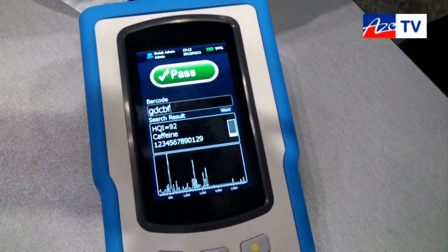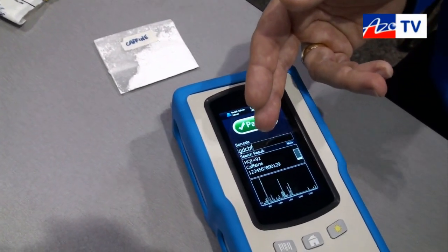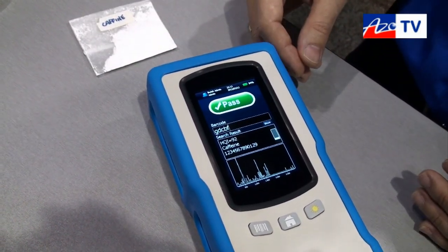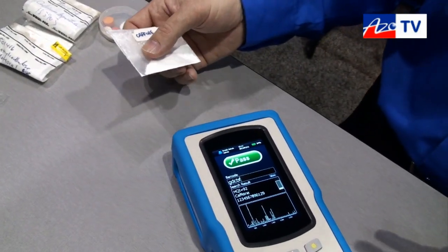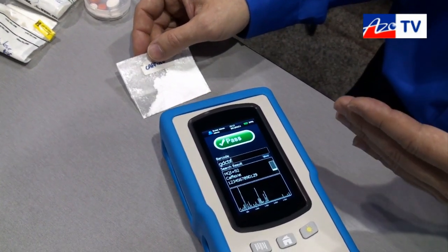Within seconds you have your answer. The product has been identified as caffeine — and that is what it is. You can see the system provides what is called HQI, the Hit Quality Index. It's a score indicating how good a match there is against the reference in the library. In this particular case, because there's a plastic bag, there's some contribution from that, so the score is not going to be perfect, but it's quite fast and reliable.